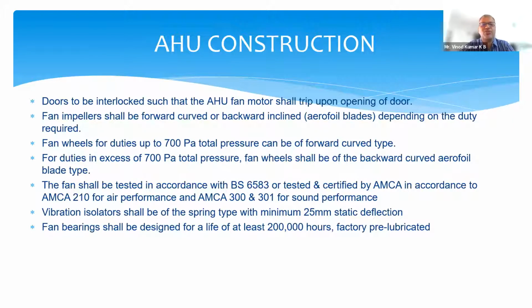Now when the fans work, what happens? They vibrate. So you need to have vibration isolators. The vibration isolation springs, generally, you should put a minimum of 25 mm, depending upon the kind of air or the kind of blower or impeller it is going to be.